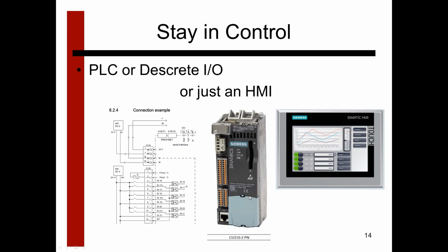Also, a lot of people don't know that you can have a drive and connect it directly to an HMI, still not needing a PLC involved. So if your application had five or six stop points back and forth, if you will, but they varied from part to part to part, you could store recipes or distances to go to on that HMI panel and be able to let an operator change those distances from the HMI panel. So you've got a very simple control indexing drive, but yet you've got an HMI panel on it, so that you're infinitely variable on your target positions, the speed that it's going to run, or anything else that you can program from the HMI. Both Kollmorgen and Siemens have example projects to get you off to the races with respect to using just an HMI, talking directly to their drive.